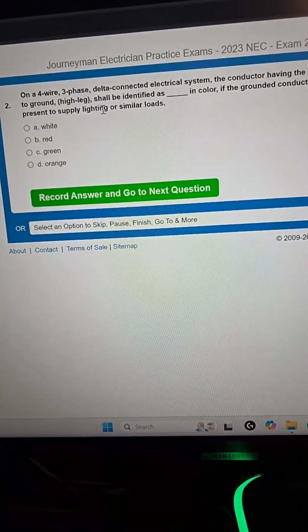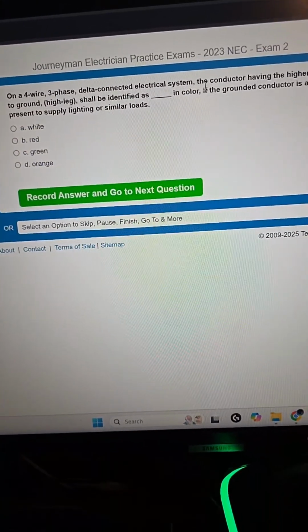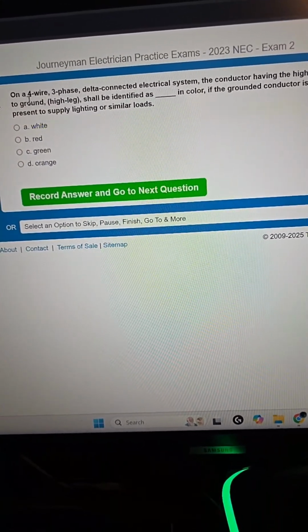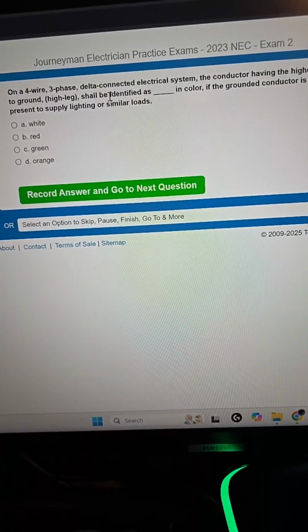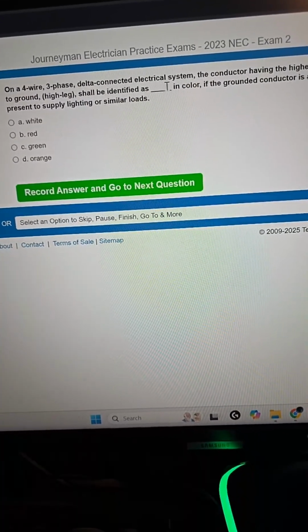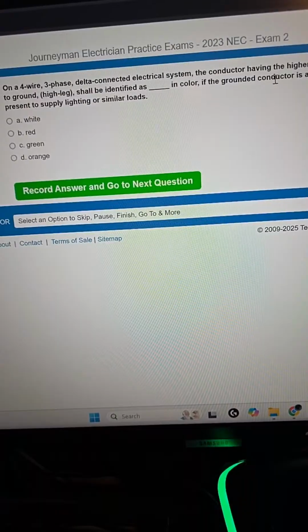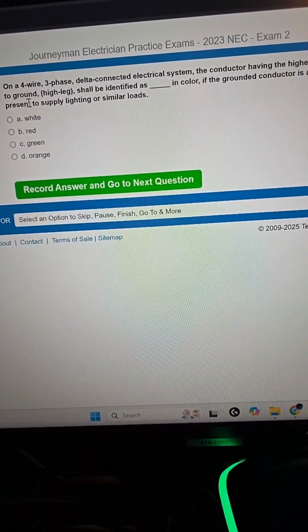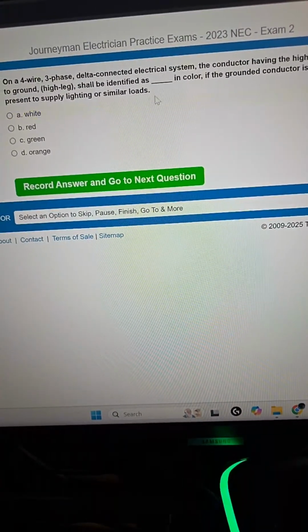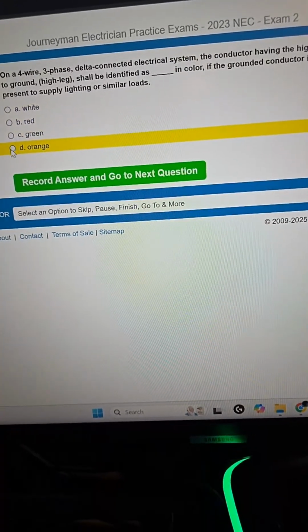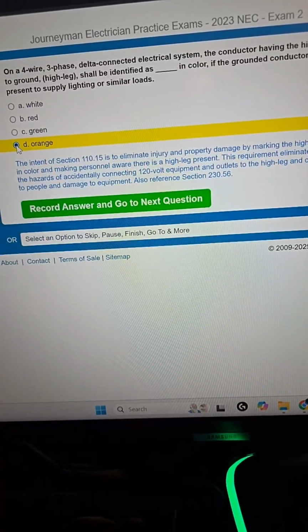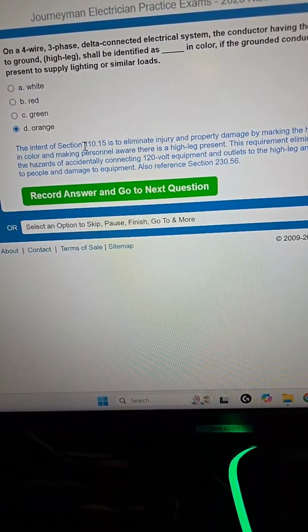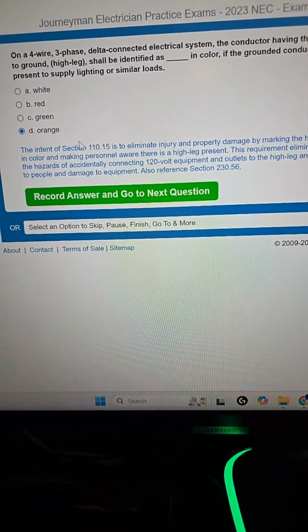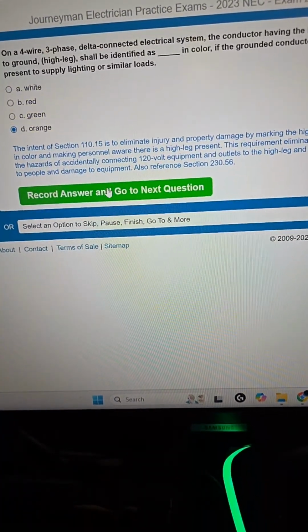Next, on a 4-wire 3-phase delta connected electrical system, the conductor having the higher voltage to ground, the high leg, shall be identified as, and it's going to say orange, if the grounded conductor is also present to supply lighting or similar loads. So we know that it's orange. I can show you where that is in the code, but it also pops up right here, which is pretty useful for you guys to study. So yeah, we're going to go next.